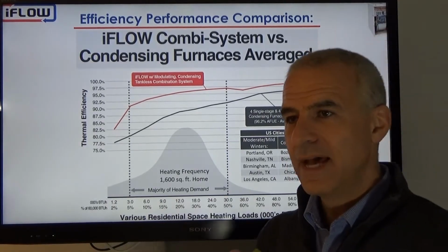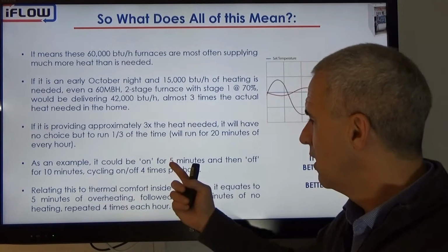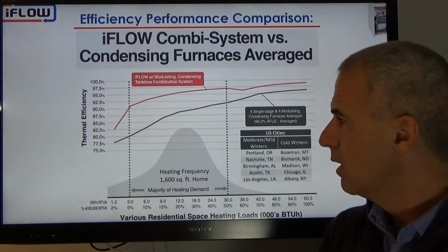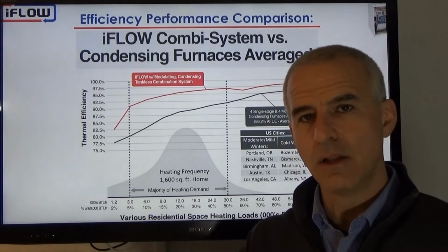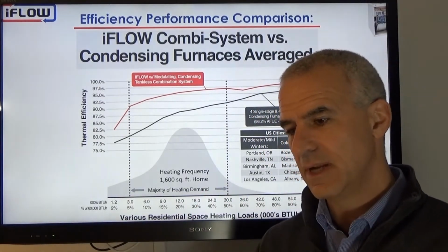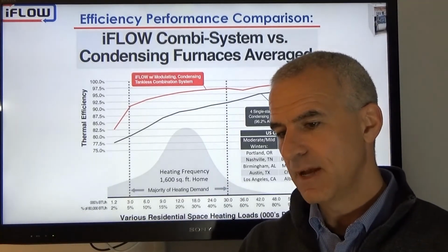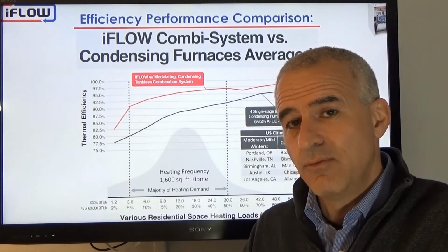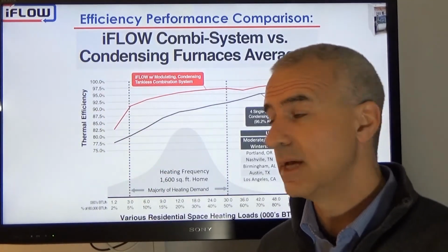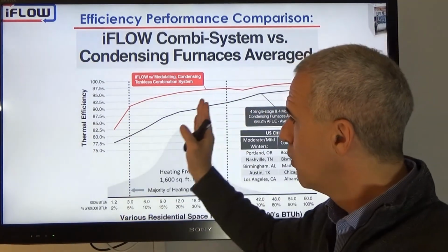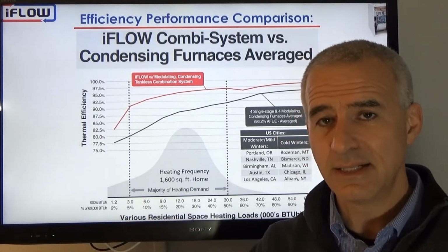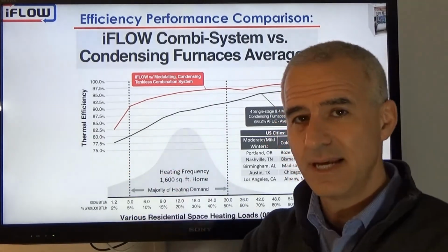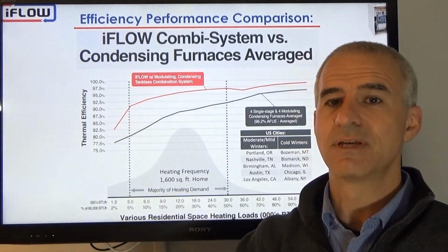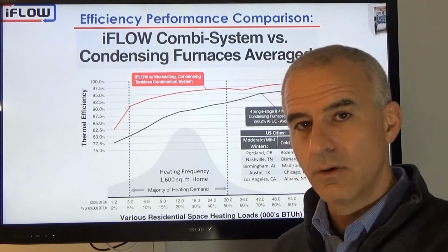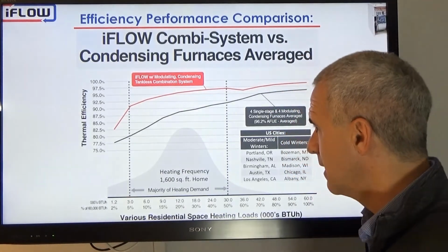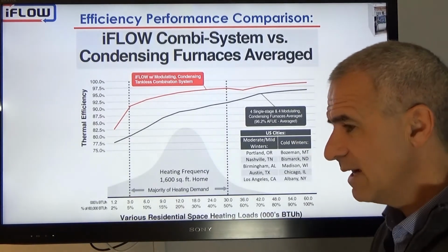So when that furnace, right, when we looked here, we're going to be cycling, let's say on for 5, off for 10, cycling 4 times per hour, well, that cycling results in losses, right? Every time the furnace has to shut down, it has to post-purge all of that heat out, and then when it starts up again, it has to heat the heat exchanger again before the blower comes on, so it doesn't deliver cold air into the house. So we see that the lower the heat load, the more the cycling with the furnace because it can't modulate. The more the cycling, the more the losses because every time you cycle, you're wasting heat on the post purge, and then you're using more heat on the startup. So how much more? Well, we've actually modeled this.